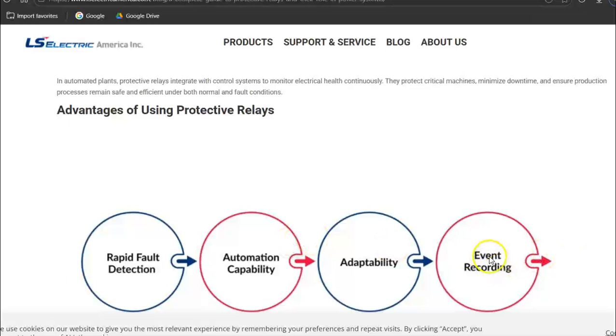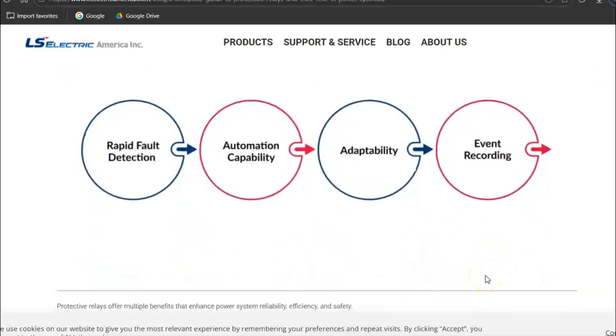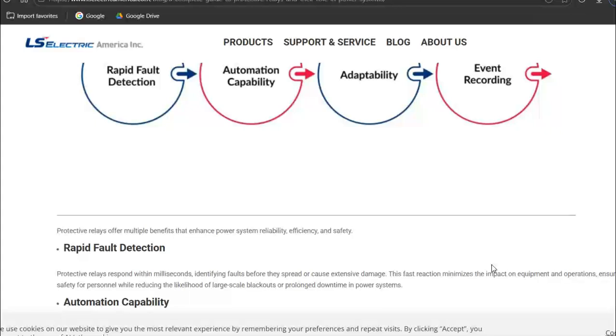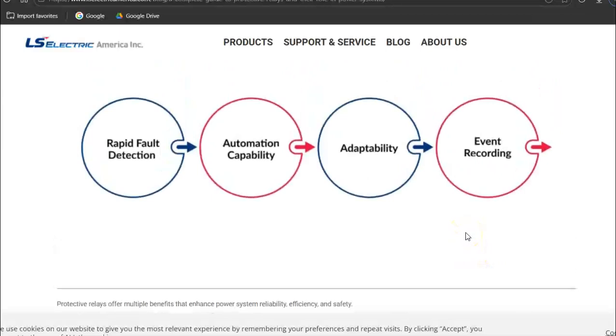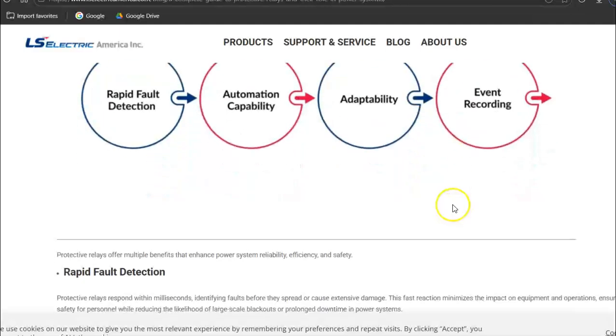They have event recording, data logging, and from a distance, everything is Ethernet. These can be in a remote location, and from a control room, you could reach out and upload all of the data from that device. Any kind of tripping information, you could monitor the currents, see the highs and the lows. And so it just gives you much, much better control. And then you can fine tune the tripping points of all these devices. The last thing you want is your main substation or main power supply tripping and shutting everybody down. You want the localized protective relays that are the closest to the fault to be the fastest ones and the first ones to trip, so that everybody else still has power.